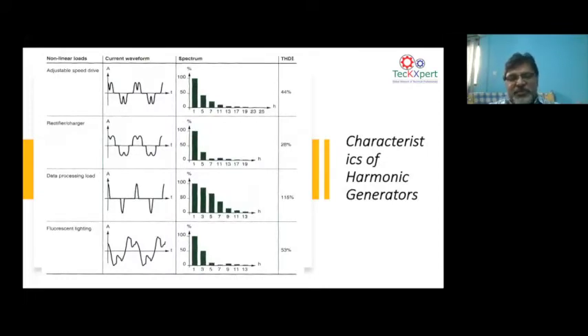Now, to sum up whatever I said before, in the summary of the whole thing, as you can see, there are different wave shapes, the current waveforms, and for each current waveform, in the frequency domain, you can see the frequency spectrum. For example, a VFD produces fundamentally 5th, 7th, 11th, 13th, and a rectifier. I can call it, maybe this could be connected to any rectification that is done to create a rectifier from AC to DC. You can see the rectifiers create 5th and 7th. All your office equipment, including your computer, fax machine, servers, can produce a wave shape like that, which can have a lot of 3rd, 5th, 7th, 9th harmonic. Your LED and fluorescent lighting can cause a lot of 3rd harmonic.